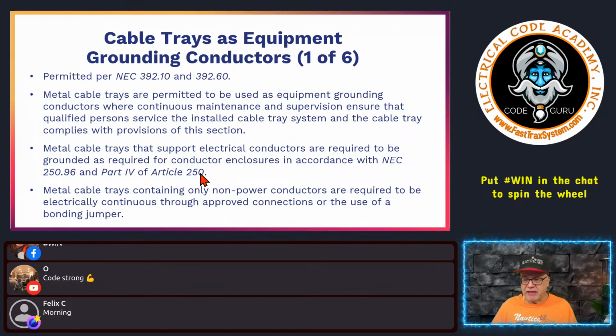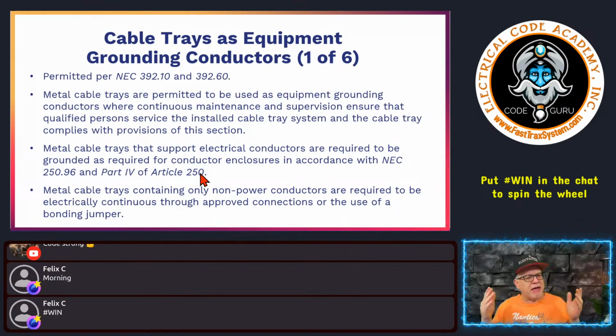So again, you're going to have to follow all of your normal bonding requirements. Make sure you make everything up. Usually they get bolted together, unless you have two parts that are not continuous, meaning you have a gap or something. Then you're going to have a bonding jumper that's going to go over that in order to make it continuous. Okay, so you might have to look at that. So the moral of this story: if you've got conductors or cables inside of a cable tray, you have to bond it. It's metal. You have to make sure it's all bonded up. Okay, with your bonding jumpers where necessary.